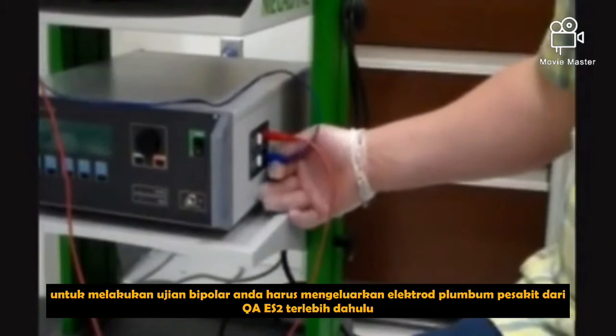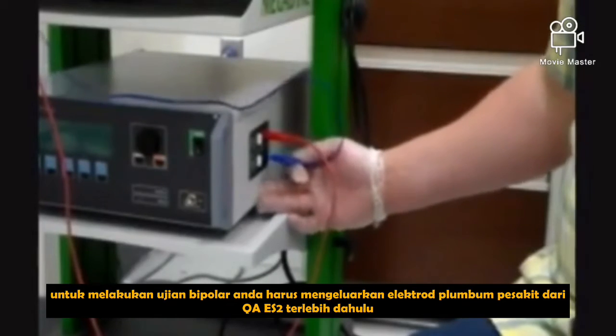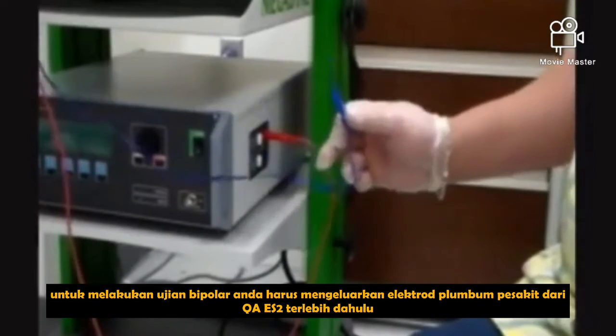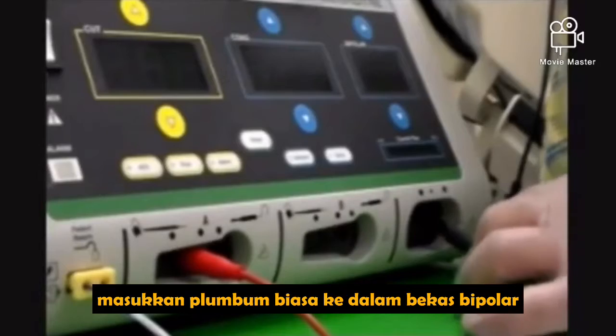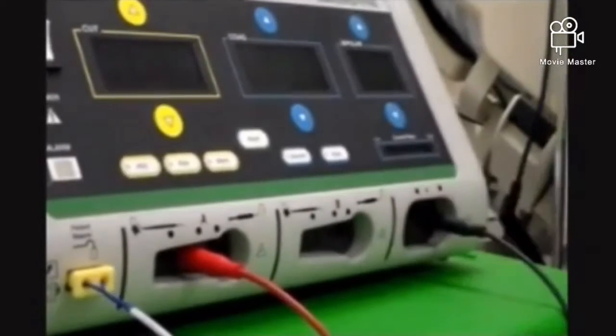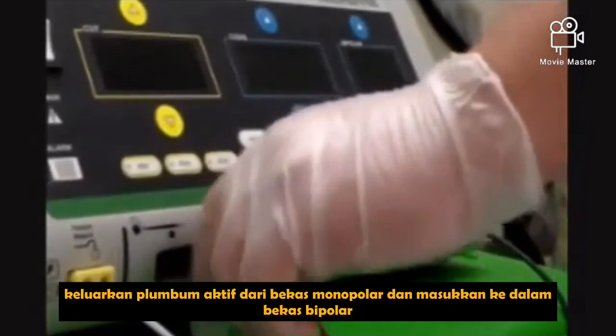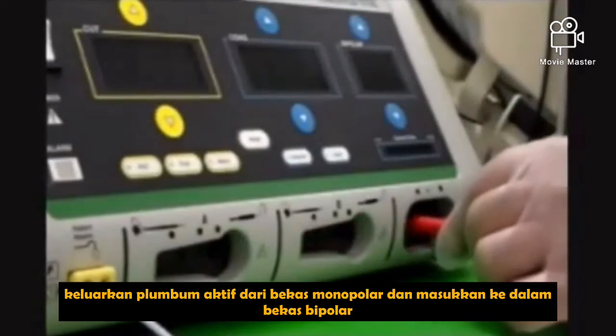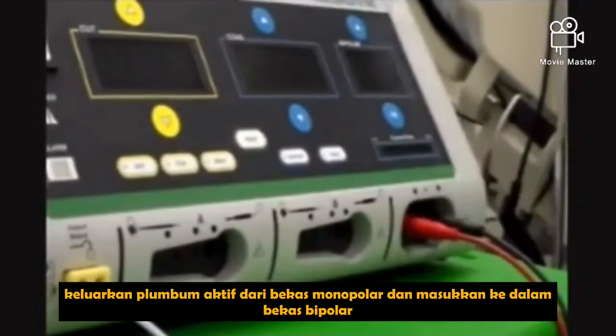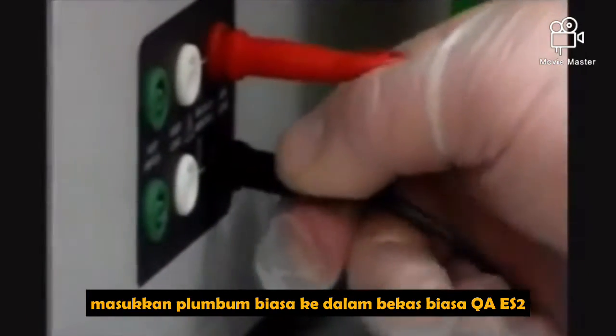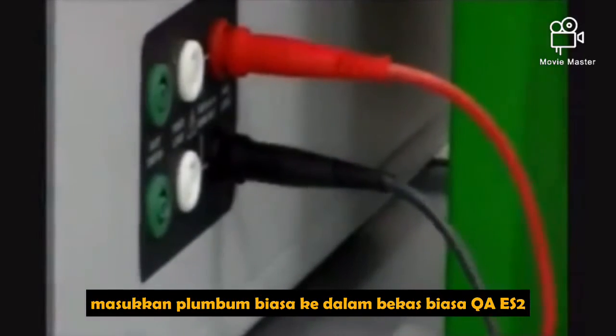To perform bipolar testing, you should first remove the patient return electrode from the QA-ES2. Insert the common lead into the bipolar receptacle. Remove the active lead from the monopolar receptacle and insert into the bipolar receptacle. Insert the common lead into the common receptacle of the QA-ES2.